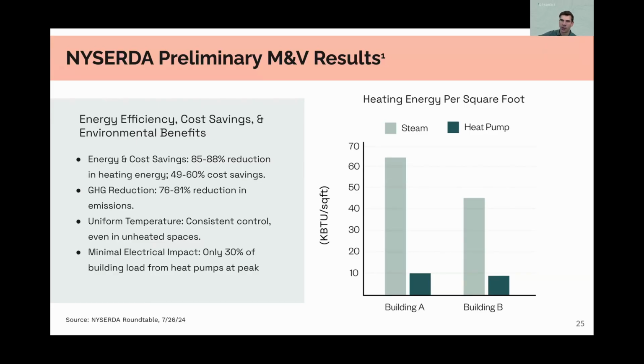As I mentioned, if you have a radiator, your thermostat is opening the window. Maybe another 10 to 20% for having local control and not heating or cooling the whole building, but having a terminal in each room. Add that up, you'd expect to reduce energy use by 85% or more, and that's actually what we measured.